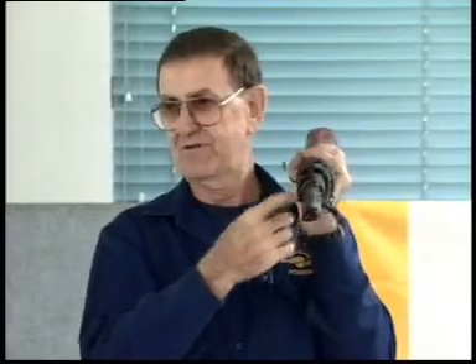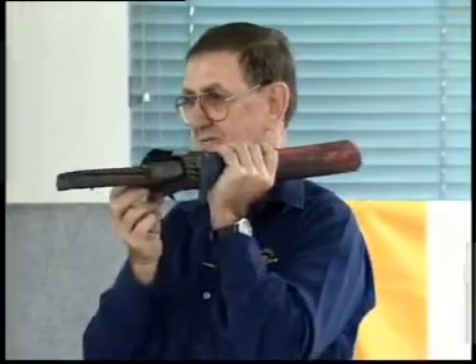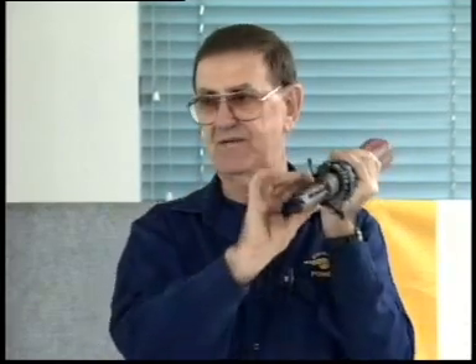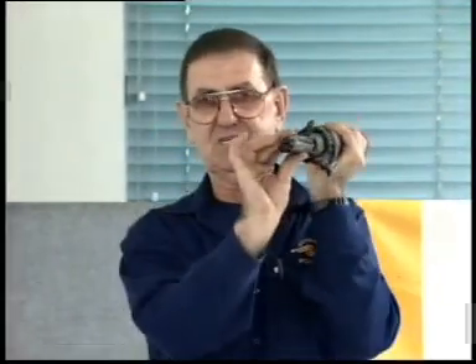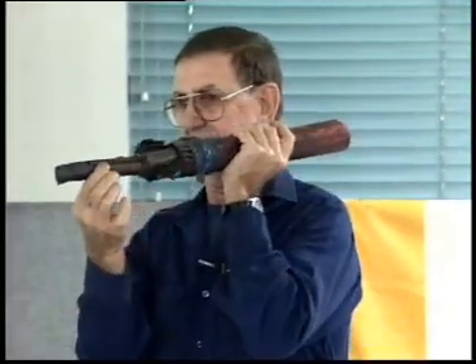Those conductors are wrapped in paper. They're not wrapped in any sort of insulating material like we have here, like this rubber. They're wrapped in paper. The important thing to remember about this is that the paper is impregnated with a special insulating oil. Around those 3 conductors, there's paper wrapped around the whole lot as well, which is also impregnated with insulating oil. The thing here we don't have inside here is any earthing like we had in those other cables. We don't have the 3 earths going through the middle, and we don't have any semiconductive material. So we have 3 phases sitting tightly knitted closely together.